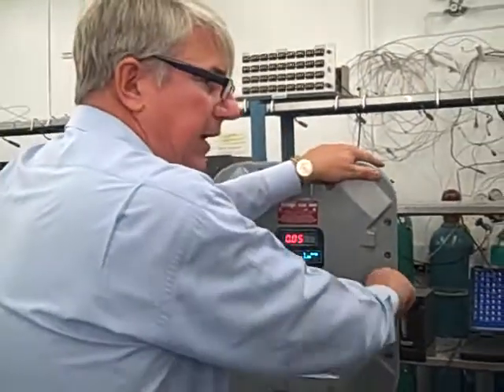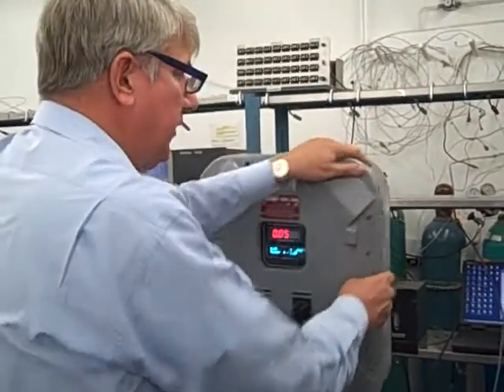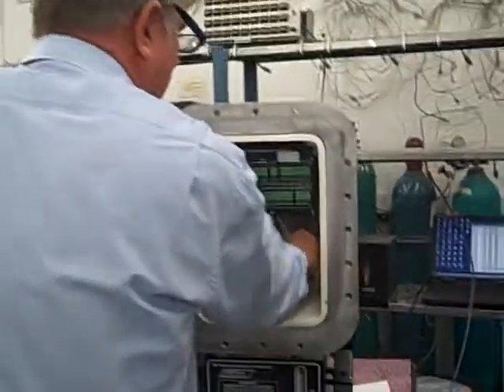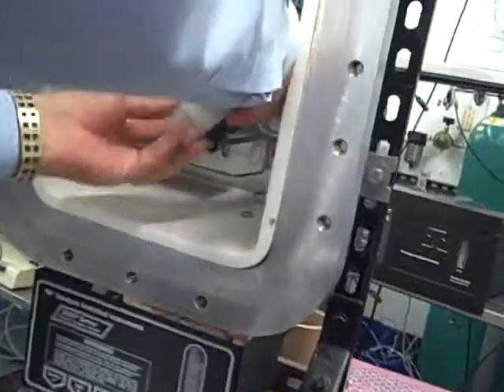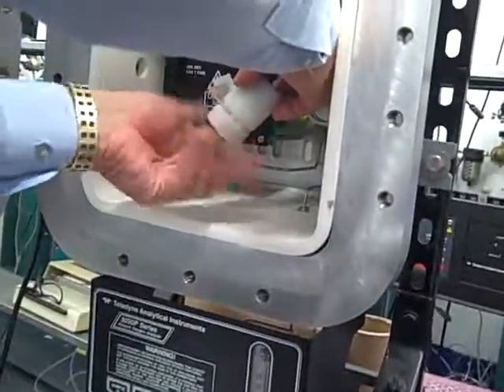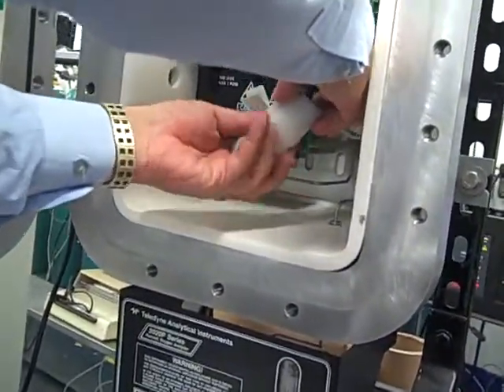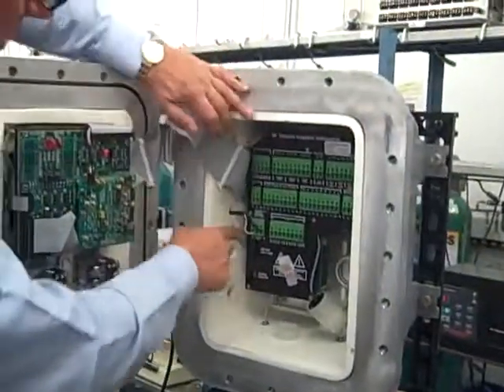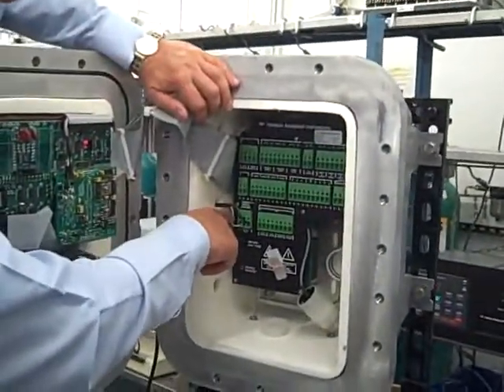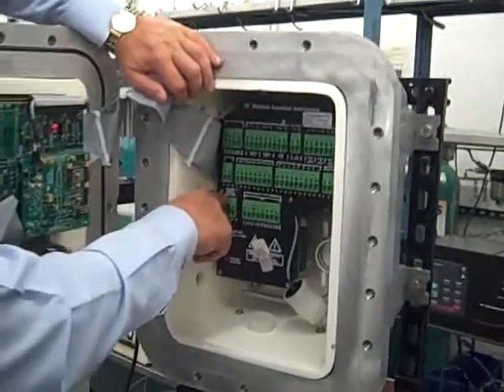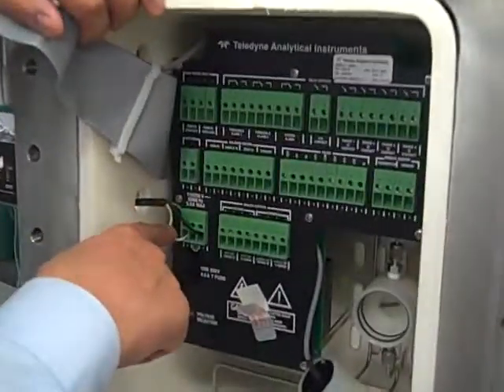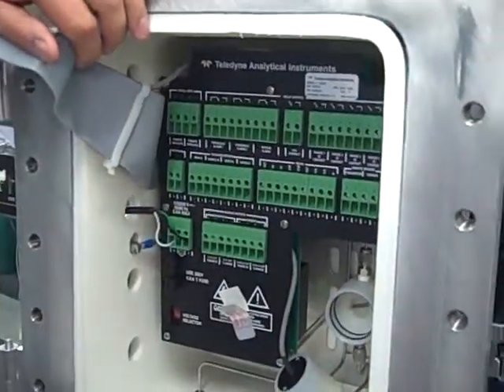Now the first thing we're going to handle is sensor installation. These units come with a sensor that is in a separate bag. In this case the sensor's installed, but let's walk briefly through sensor installation, because this is the first thing you're going to need to do once you get this unit all wired up and powered on AC. Oh, one thing I forgot to mention, those are the AC terminals there. The universal power supply, 115, 230 volts AC. Make sure that's connected properly.